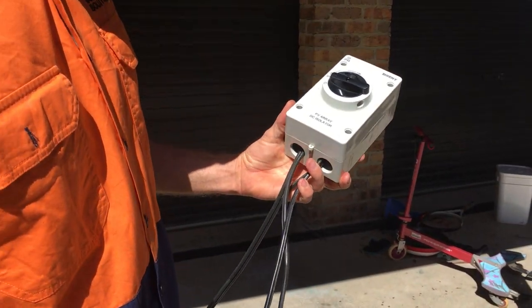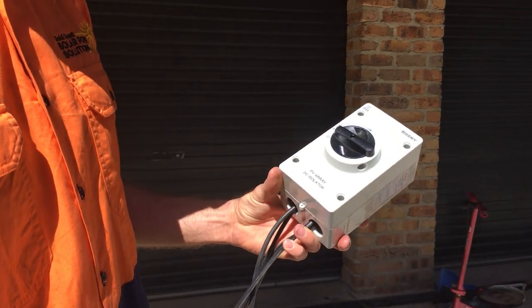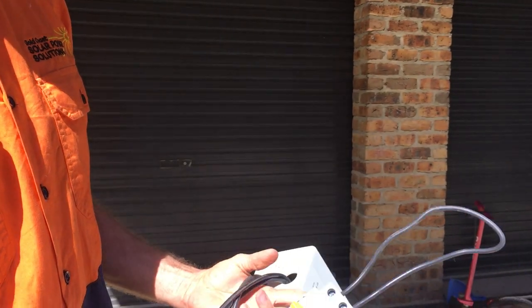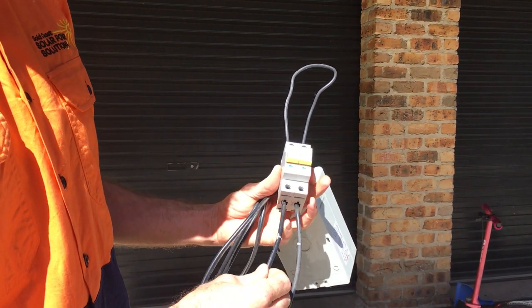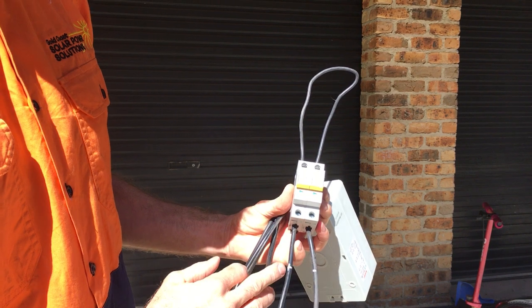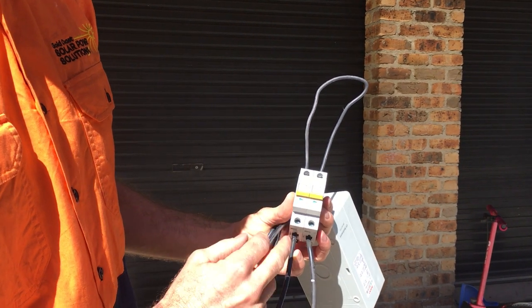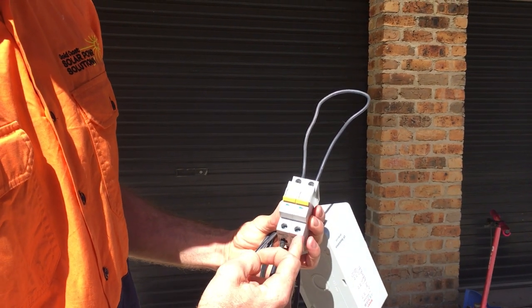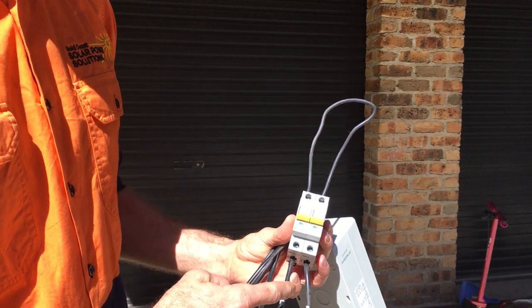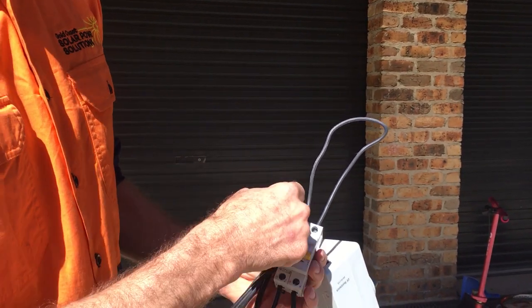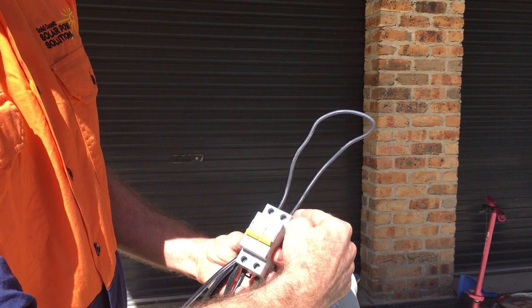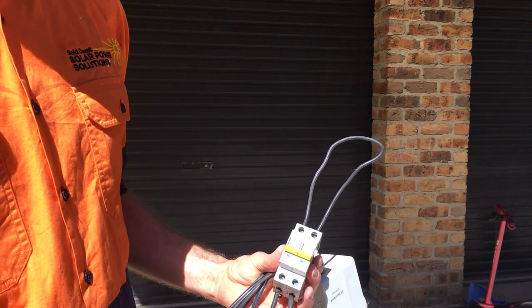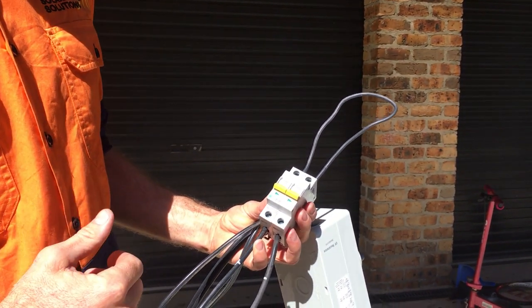I've got a DC isolator here, which is wired all correctly. Then we've got our positive coming into this circuit breaker, but you see I've gone into the negative terminal here, and the negative from the solar panels goes into the positive. So this is actually wired reverse polarity at the moment. And what I've done is I've just run a wire across here to actually short circuit the circuit breaker.